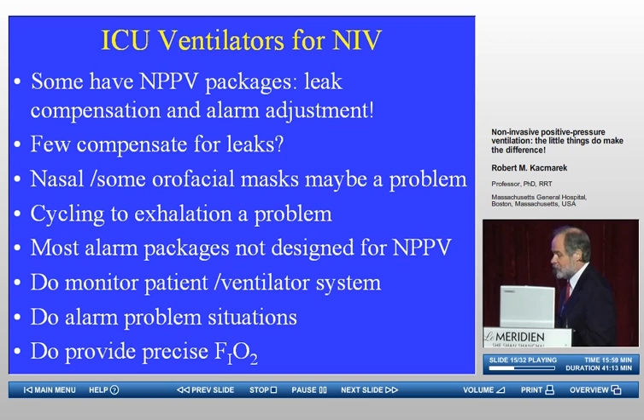In general, I would say that you have to be careful with the type of interface that you use. Nasal masks and the oral facial masks that have leak ports built into the mask or have one-way valves that are used for allowing the patient to breathe to atmosphere if the tubing should become disconnected, as exists for many of the bi-level pressure ventilators, tend not to work well with ICU ventilators. You have to use a mask that has no expiratory port on it, no one-way valve in that mask for it to function with maximum efficiency with an ICU ventilator. The big problem with these units is cycling to exhalation, and I'll talk about that in detail. However, alarm packages could or could not be designed for non-invasive ventilation depending upon their addition of these non-invasive modes. They do monitor patients well. Clearly, they are alarmed to meet the needs, and they do provide very precise and consistent FiO2. So there's pluses and minuses with both of these units.